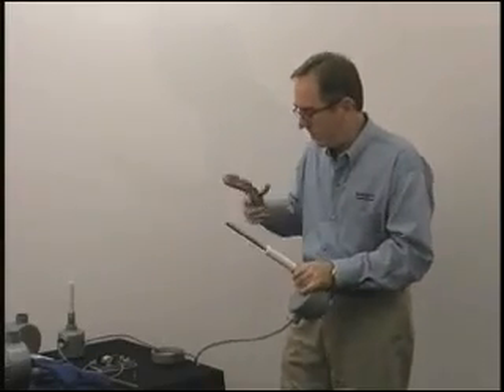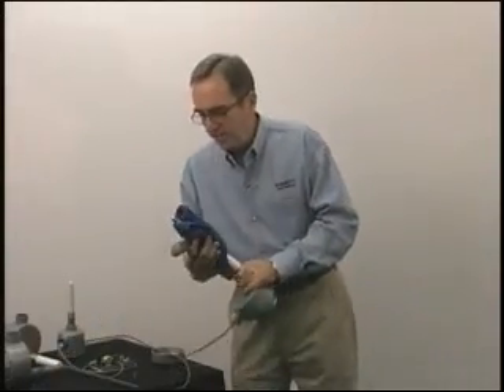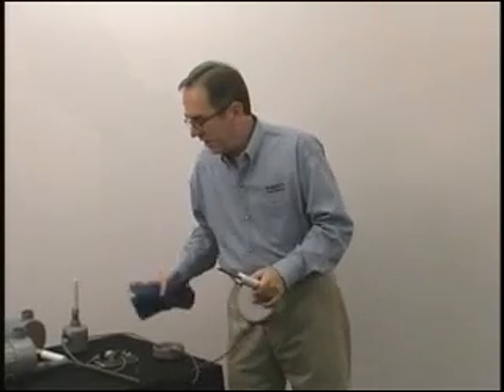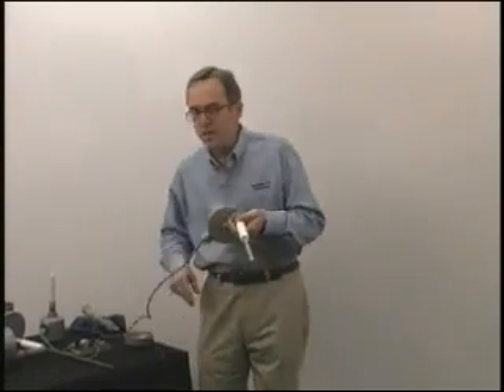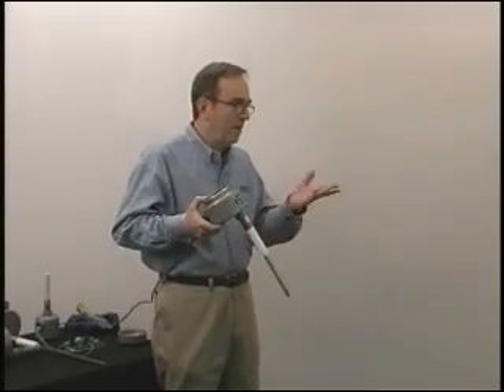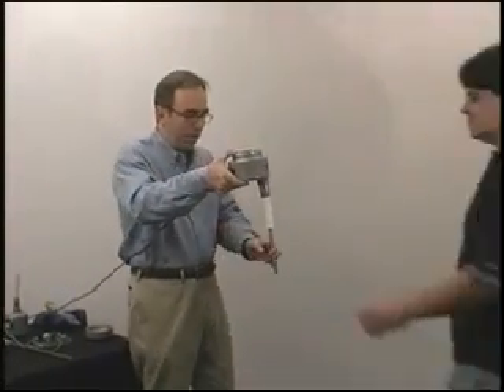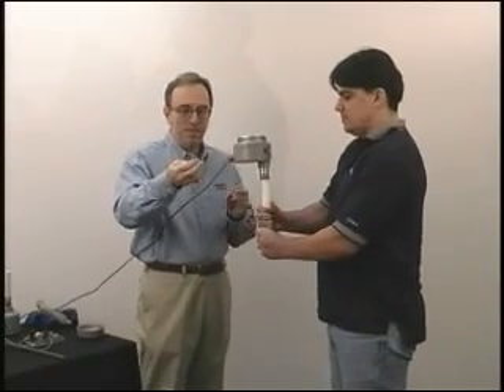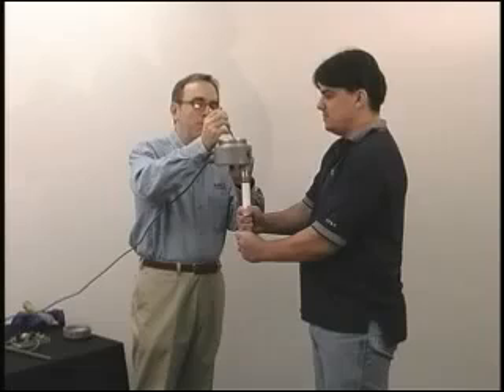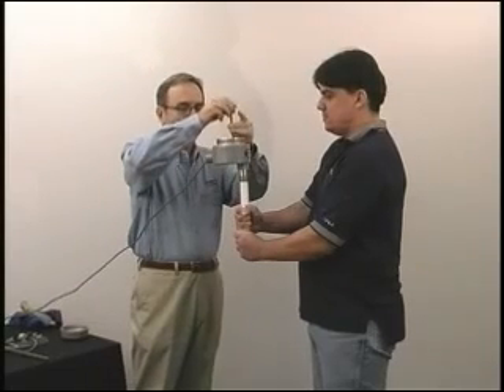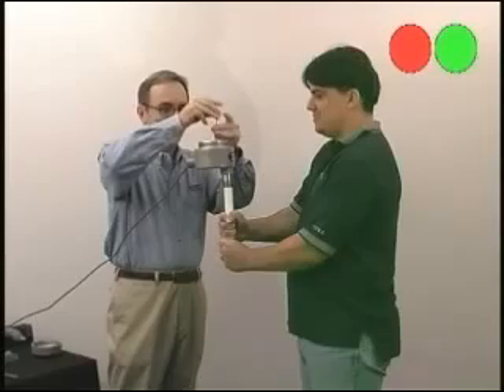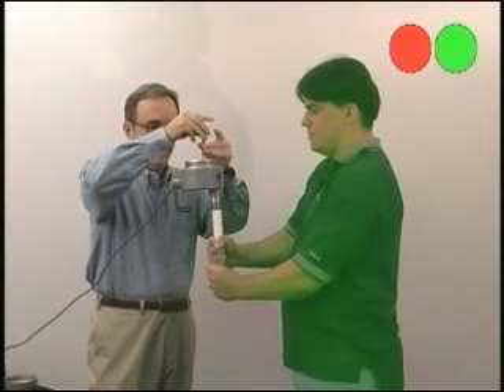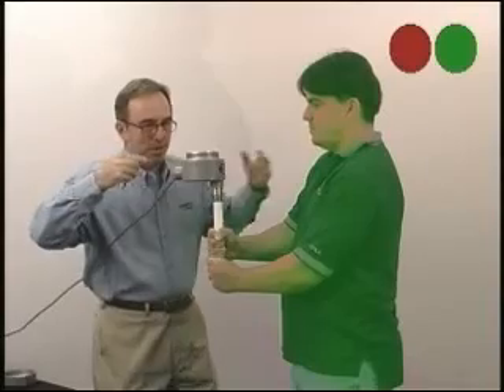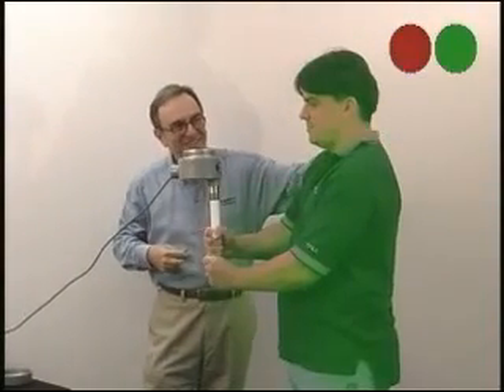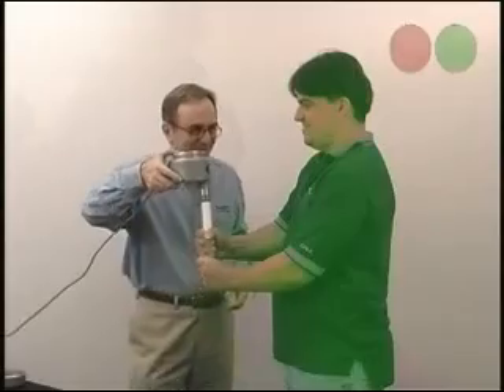If you ever had so much material on the probe that it gave you a false alarm, there's no need to go in and clean the probe off. What you can do is recalibrate it to the amount of material that's stuck on the probe. And to give you an idea of the tuning range of that, if I could get you to hold onto that probe with both hands, support the weight of the unit. Now what I'm going to do is I'm going to tune you out. You're a false alarm, excess product buildup in the tank. And what I'm going to do is tune you out. Now when I pat you on the back, see, the unit actuates. Thank you. This has the widest tuning range of any switch on the market.